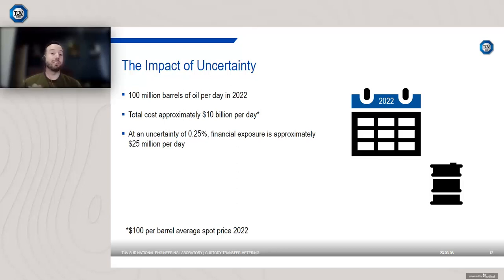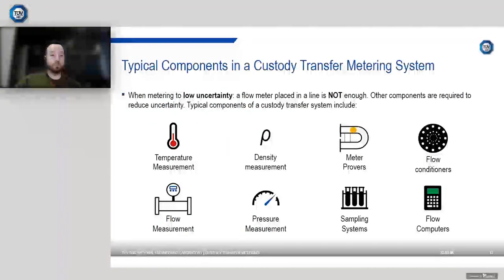So the reason you've got uncertainty targets is to limit this financial exposure. So that's the financial exposure at 0.25%. You can imagine if you've got poor measurement quality and your uncertainty is double that or triple that, the financial exposure just increases. So it suits all parties to target as low an uncertainty as possible when you're doing custody transfer metering.